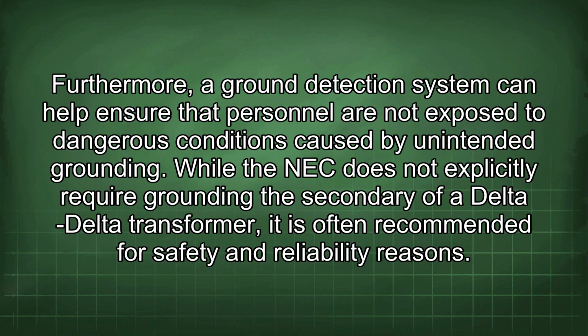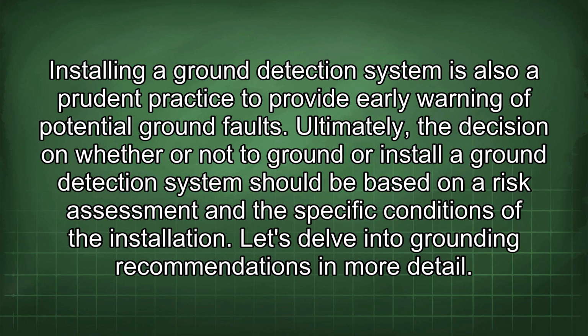Furthermore, a ground detection system can help ensure that personnel are not exposed to dangerous conditions caused by unintended grounding. While the NEC does not explicitly require grounding the secondary of a delta-delta transformer, it is often recommended for safety and reliability reasons. Installing a ground detection system is also a prudent practice to provide early warning of potential ground faults. Ultimately, the decision on whether or not to ground or install a ground detection system should be based on a risk assessment and the specific conditions of the installation. Let's delve into grounding recommendations in more detail.